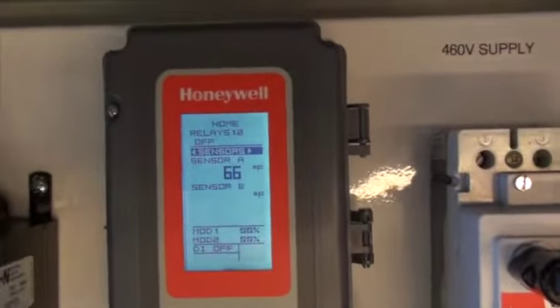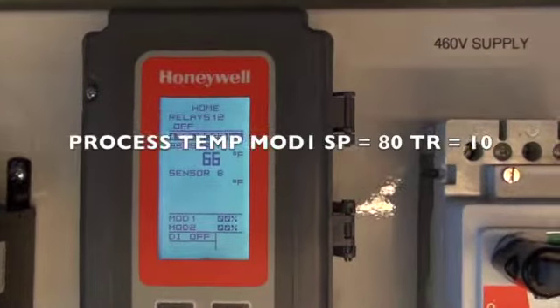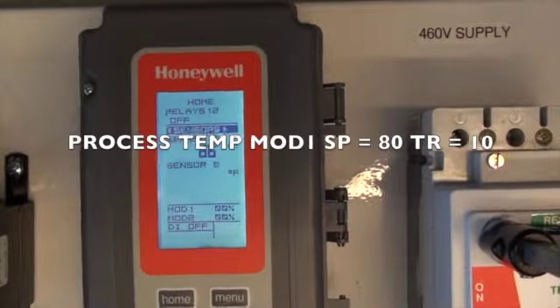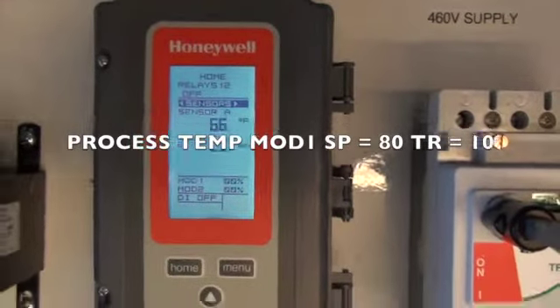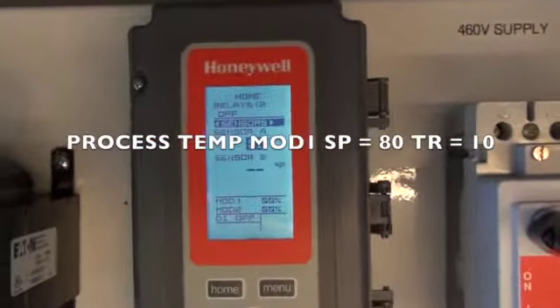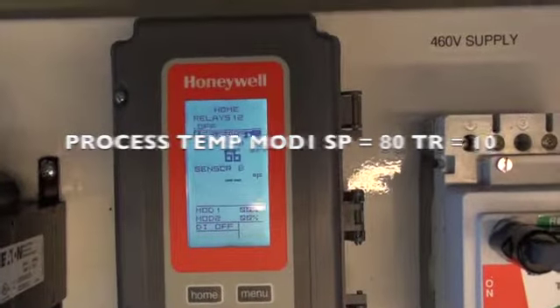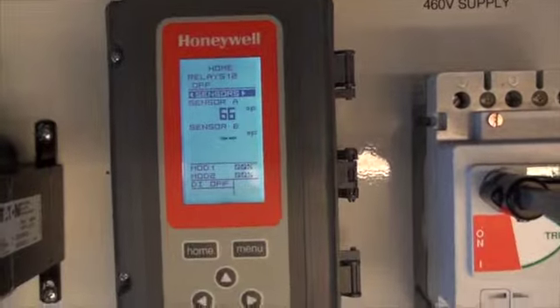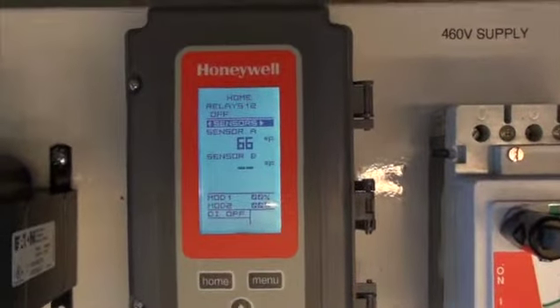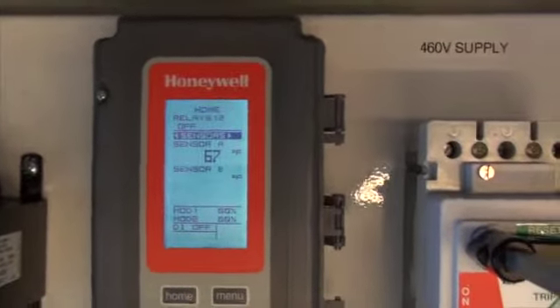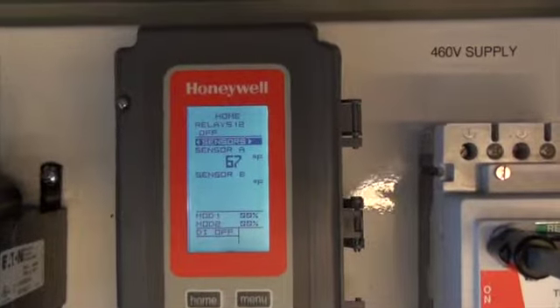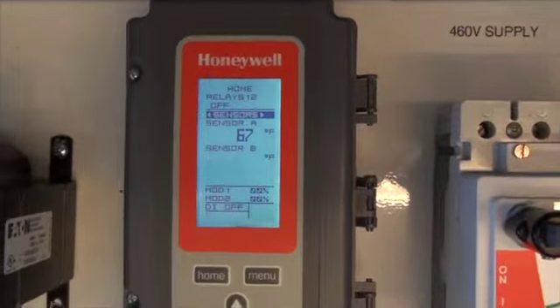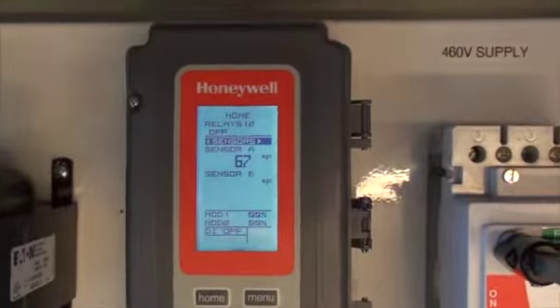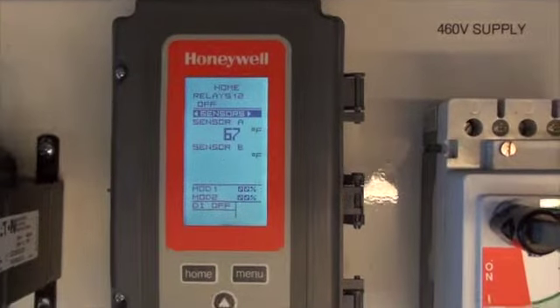Remember the key factors. The key factor is set your modulating output. You're modulating one output to whatever the process loop temperature you want to maintain. In this case, I set it to 80 degrees. And then set your throttling range, I would say 10 degrees if you want to, because it gives a nice smooth ramping up and down. If you want a tighter control, set it to 7 or 8 degrees. But if you want a looser control, set it to 11 or 12 degrees. But typically 10 degrees works in most cooling tower applications for your throttling range on your modulating output.